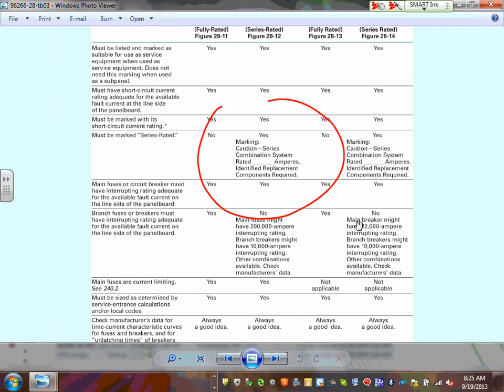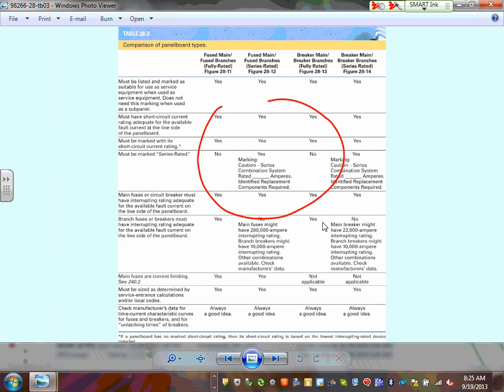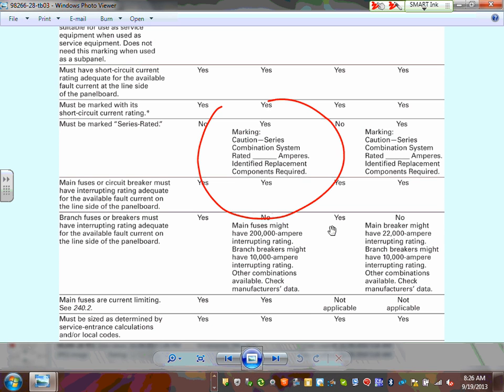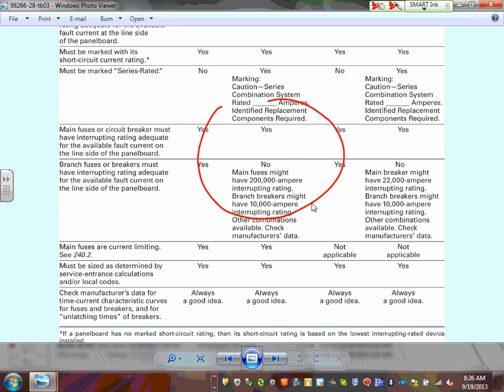The interrupting rating of the circuit breaker must be high enough to interrupt the available short circuit current. Many fuses are current-limiting; circuit breakers typically are not. You will be using time-current characteristic curves when doing coordination and arc flash analysis in your spring project.